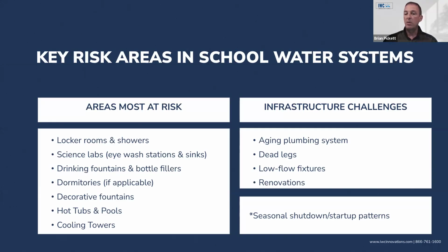Renovations, I kind of already spoke to that with the dead leg situation. Renovations are just leaving piping behind and letting water sit stagnant in there. The reason a dead leg is very important here to think about is, say you've got your piping that runs along the header there and you've got the pipe coming over and then going down the wall. Well, that water that's sitting in that pipe that comes out and goes down the wall is sitting there stagnant.